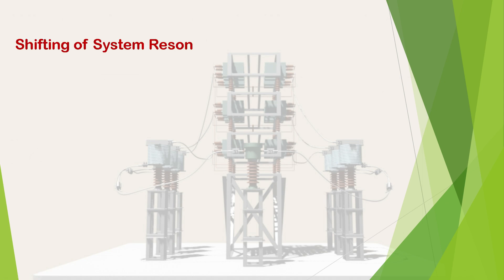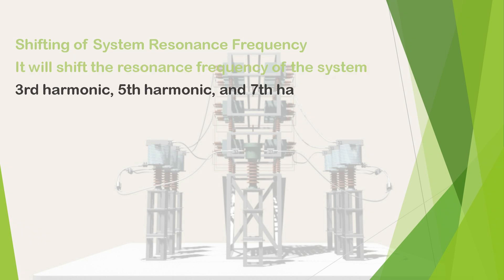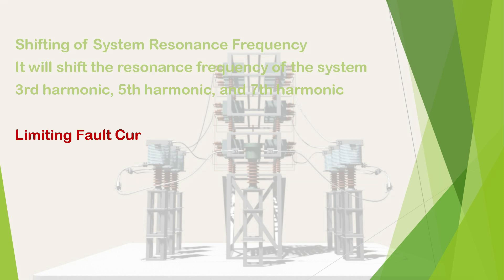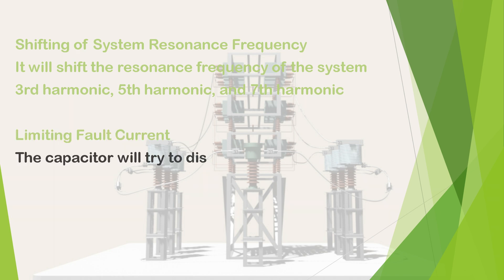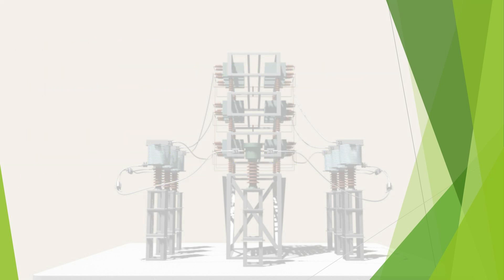This is how we use inductors with the capacitor bank to limit the inrush current during switching on. Another benefit of adding this inductor to the circuit is that it shifts the resonance frequency of the system, meaning the third, fifth, and seventh harmonics of the system frequency will be shifted, so the problems due to harmonics will be reduced. Additionally, whenever there is a fault in the power system, the capacitor will try to discharge through the fault path — and the inductor connected in series will limit this fault current and save the capacitor bank.